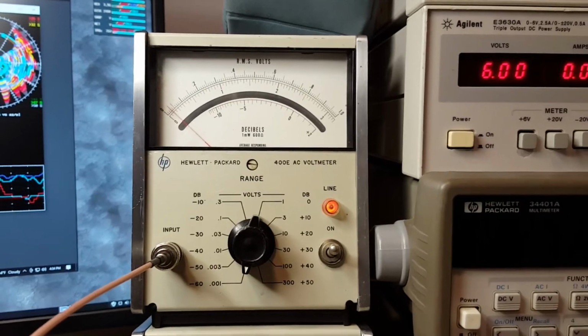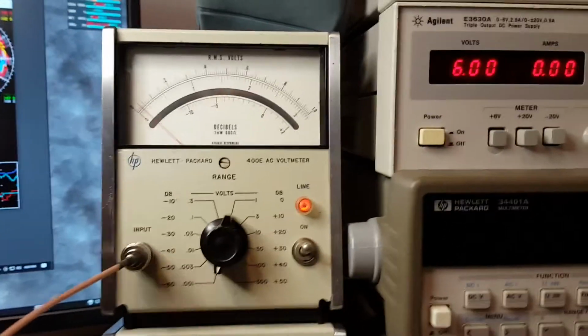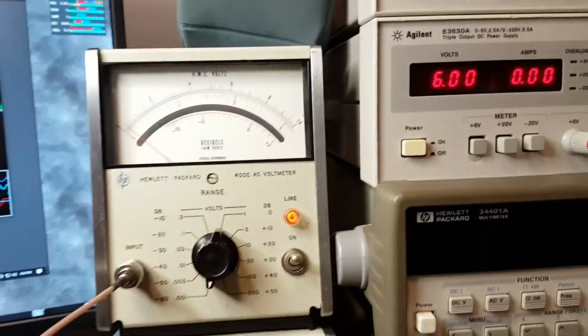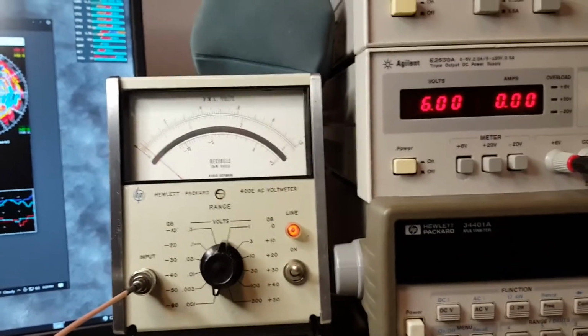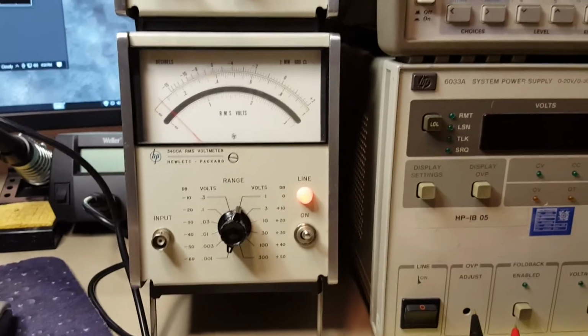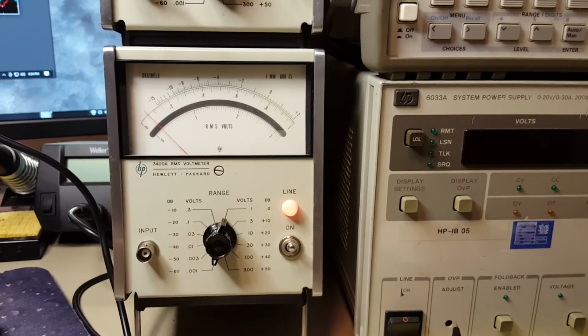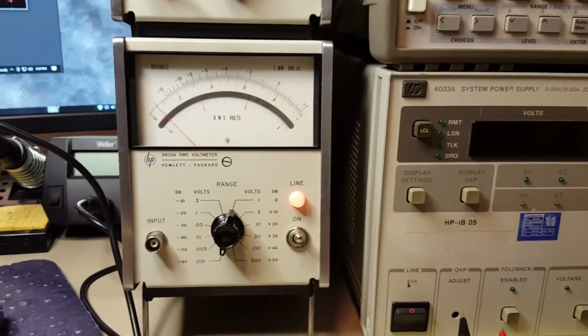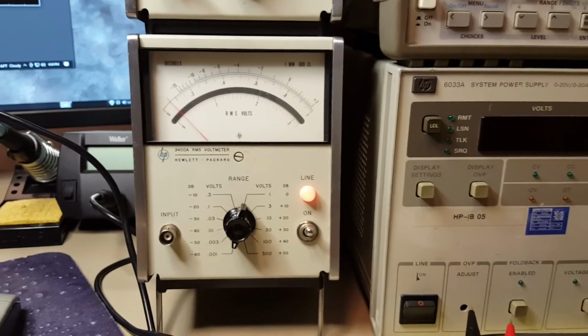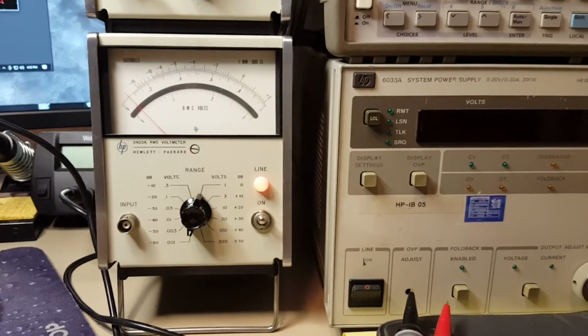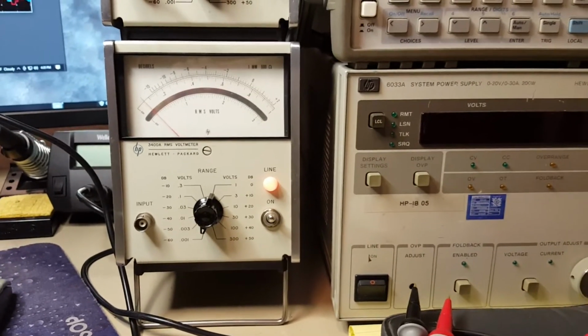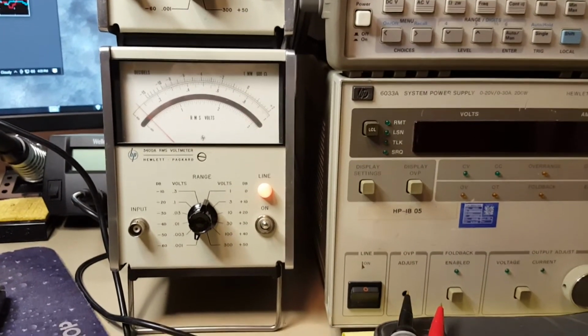And it also has to do with the meter's crest factor. This meter here is about 1.41 crest factor. This one's got a crest factor of 10, so you can really make some nice accurate measurements regardless of the waveform shape. So when you're hunting for meters, it's definitely worth your while to take crest factor into consideration.